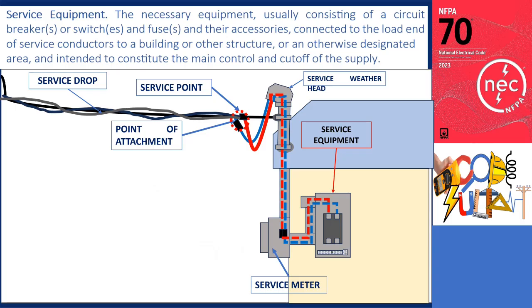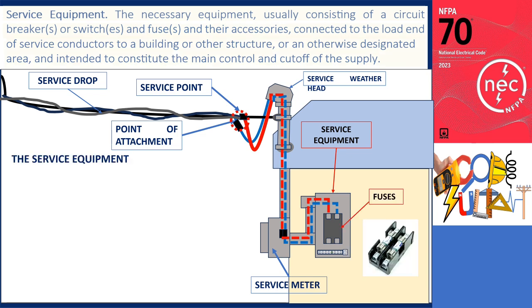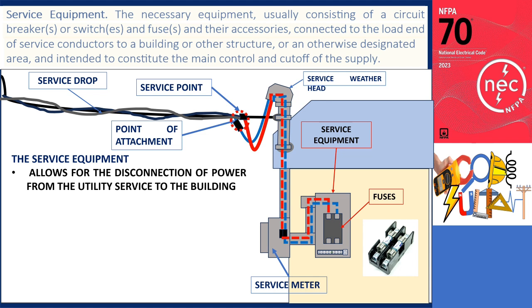Service equipment: the necessary equipment, usually consisting of a circuit breaker or switch and fuse and their accessories, connected to the load end of service conductors to a building or other structure, or an otherwise designated area, and intended to constitute the main control and cutoff of the supply. The service equipment allows for the disconnection of power from the utility service to the building, ensuring safety during maintenance, repairs, or emergencies.